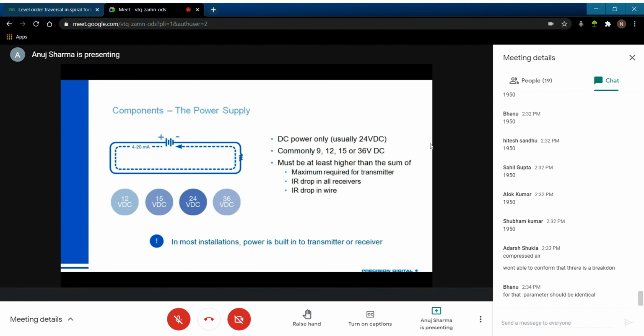Usually that's not a problem. If you don't work with any 2-wire or loop-powered devices, you may not even have to worry about this. You may not even think about it in your day-to-day affairs. However, if you're using 2-wire or loop-powered devices, this becomes really critical. You want to make sure that you're not using a 2-wire transmitter, meaning that it draws its power off of the current loop, that might require an 18-volt drop, but then trying to run it with a 9-volt power supply. Because regardless of how small the voltage drops may be in all those other pieces of equipment, that 18 volts in your transmitter is going to sink that 9-volt supply, and now all of a sudden your system's not going to work.